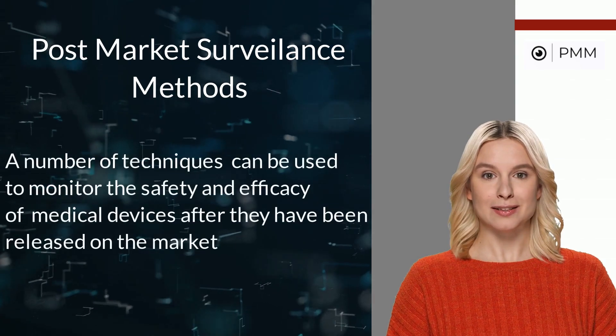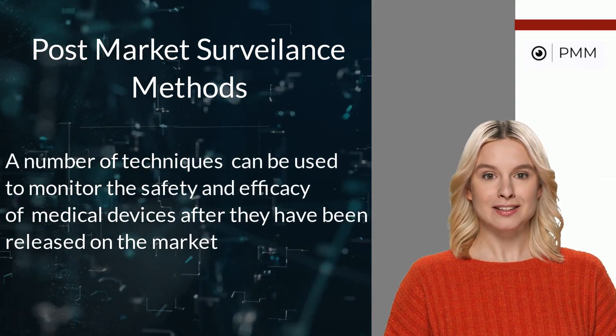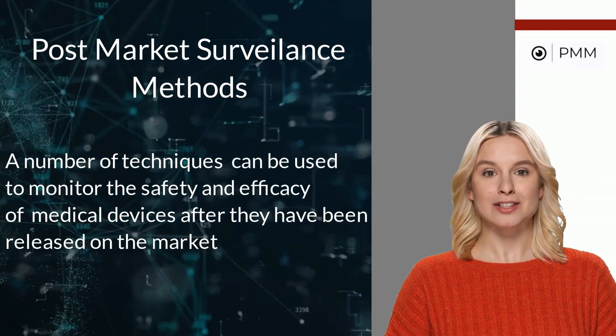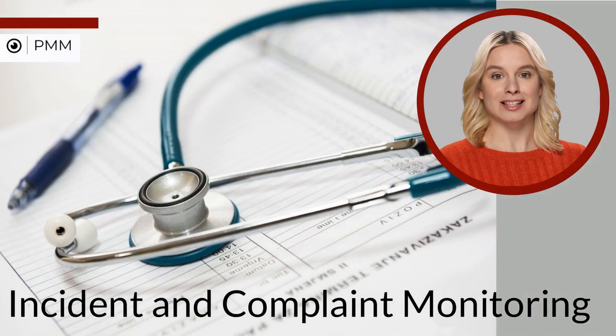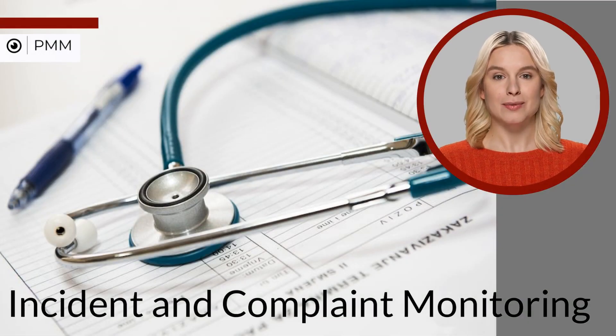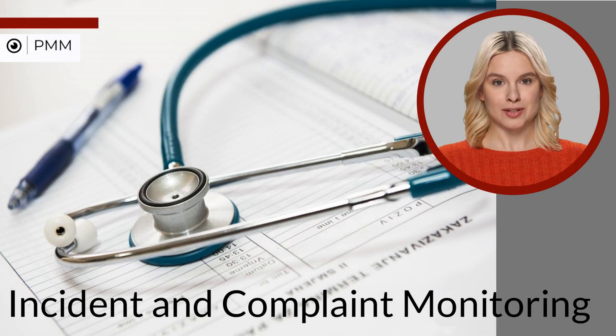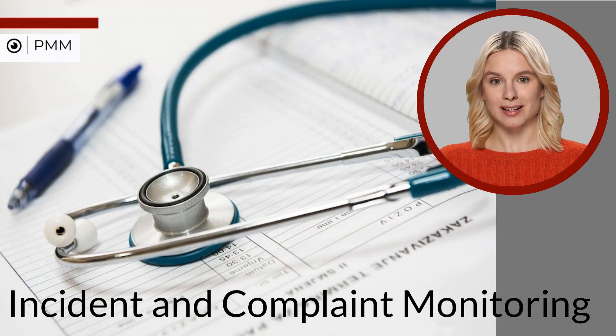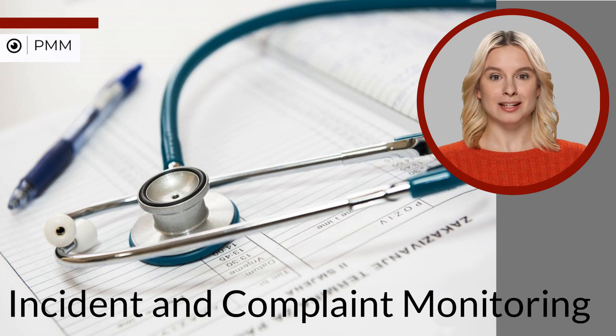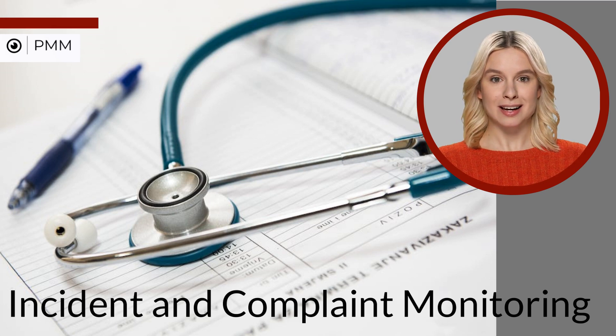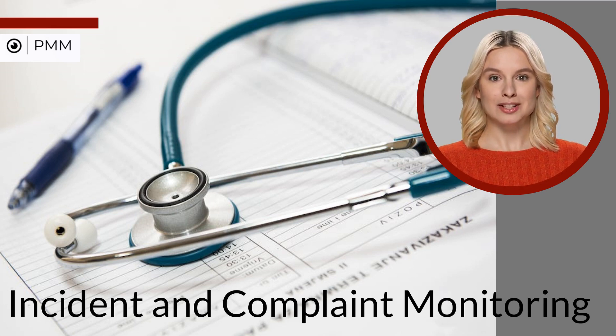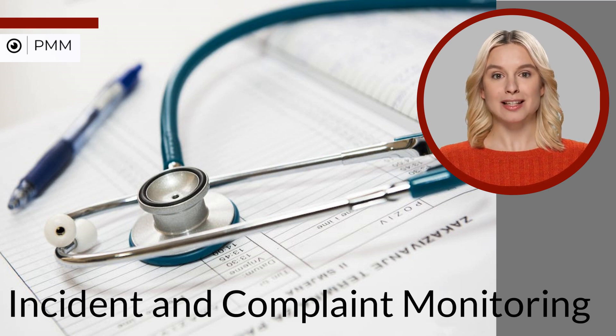There are a number of techniques that can be used to monitor the safety and efficacy of medical devices after they have been released on the market. These include incident and complaint monitoring, which involves tracking any reports or complaints about the device from users, healthcare providers, or other relevant sources. Complaints are managed as part of the quality management system to ensure they are properly documented, investigated, and addressed. Any information collected can be used to identify problems, alert regulatory agencies, and assess the need for corrective action.